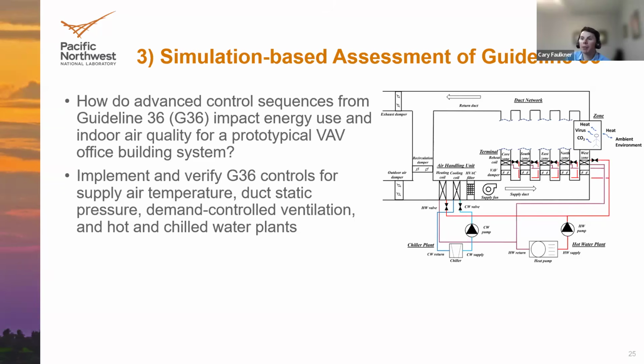And to do this, we implemented and verified G36 controls for various control set points within the system, including supply air temperature and duct static pressure. I mentioned those key aspects of the VAV air handling system, as well as demand controlled ventilation, which I'll talk about more, which controls the ventilation to the zones based on CO2 measurements, as well as controls for the hot and chilled water plants.